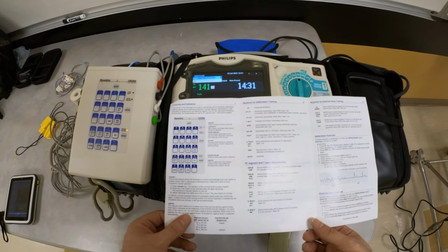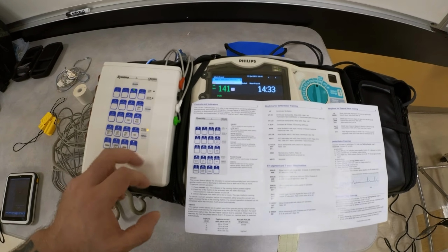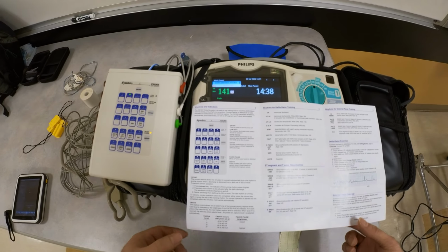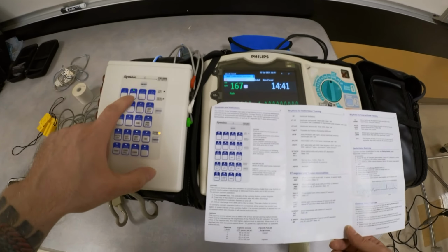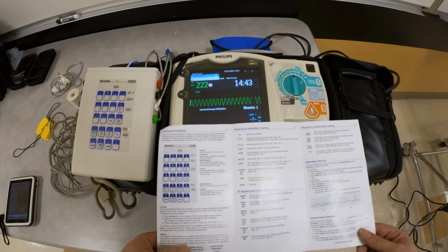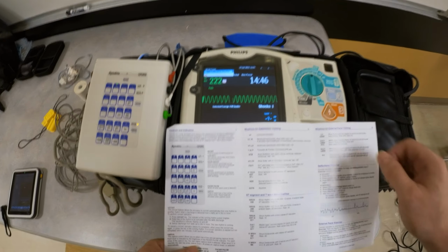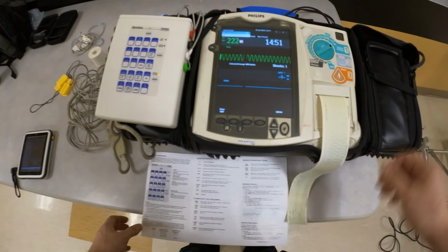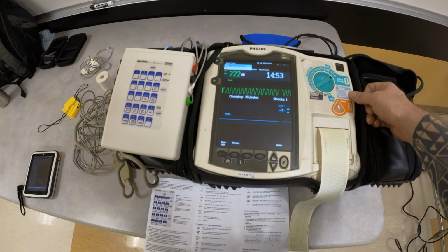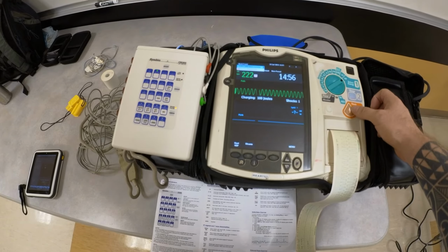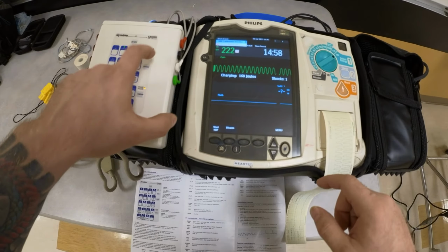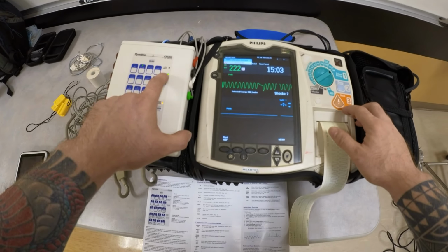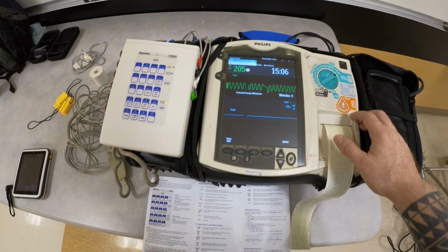So let me just go over the functions of some of these buttons if you're not familiar. Let's say I wanted to perform defibrillation. I'll put on ventricular tachycardia high, and in this scenario you could say the student does not have a pulse, and they begin their CPR. So they'll put it at max joules. They will go ahead and charge, right? And once they defibrillate, if your joule setting is above 50, you will see the discharge light up whenever the student performed this procedure, right? So there was successful defibrillation sensed.